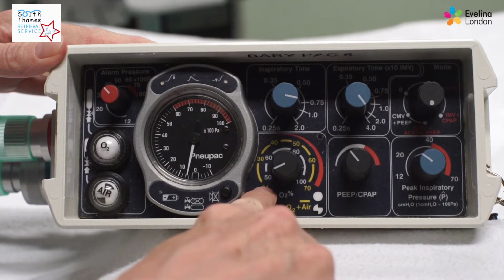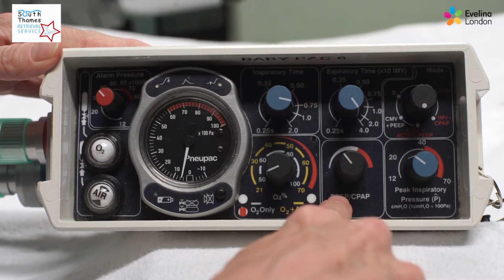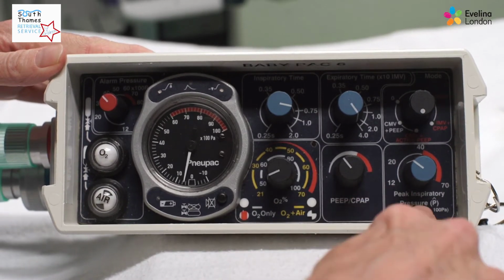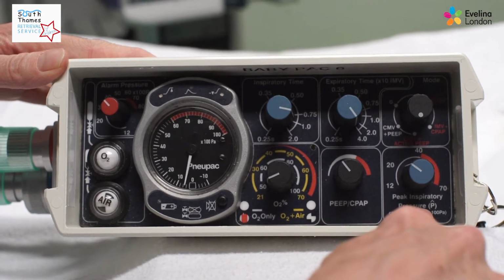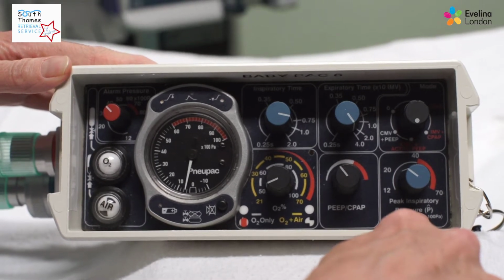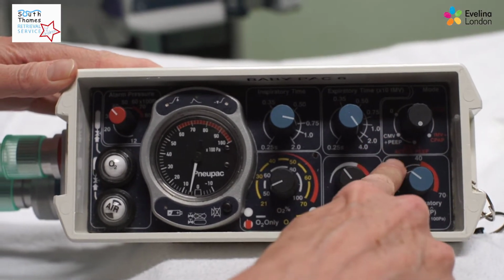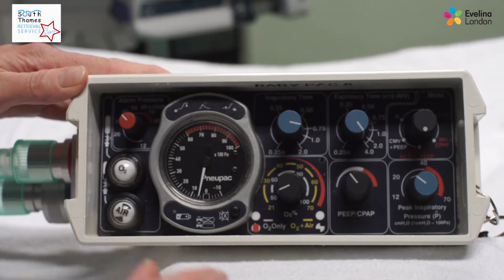With CMV and active PEEP, PEEP is maintained between breaths. When we change it to CMV with PEEP, in between breaths the ventilator isn't delivering a constant PEEP. CMV and active PEEP is the mode that we prefer.